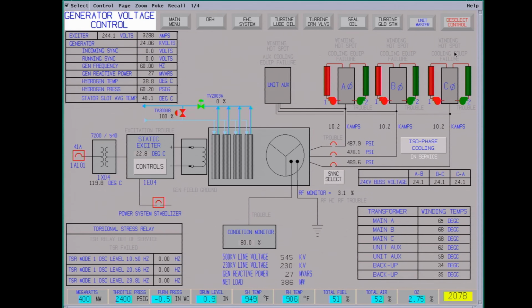You have winding hot spots, equipment cooling failures. There's quite a few different protection circuits on this. We won't mention much. Isophase cooling. This is blowing air down this isophase duct. It's one conductor inside of a pipe feeding each transformer, stepped up.